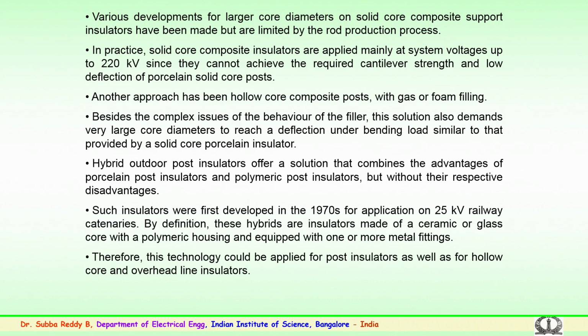These insulators were first developed in the 1970s, almost 50 years ago, for application in 25 kV railway catenaries. This hybrid technology was tried out for railways or traction. By definition, hybrid insulators are made up of a ceramic or glass core in the middle, with a polymer housing, equipped with one or more metal fittings. This was developed for 25 kV applications.